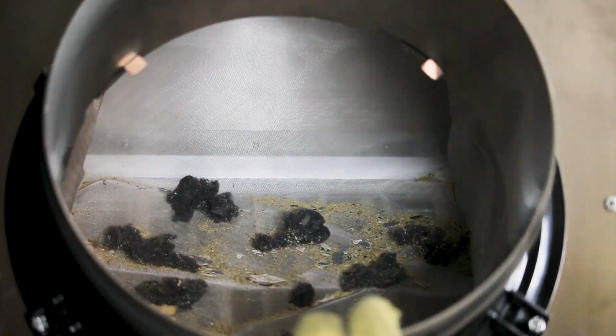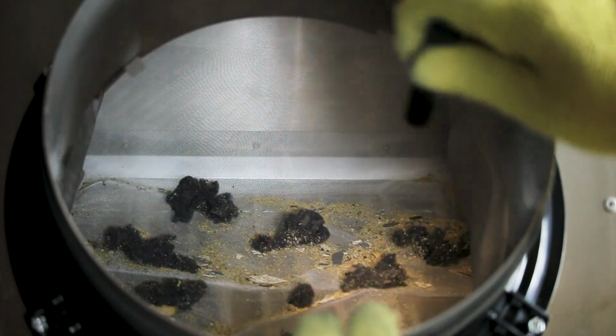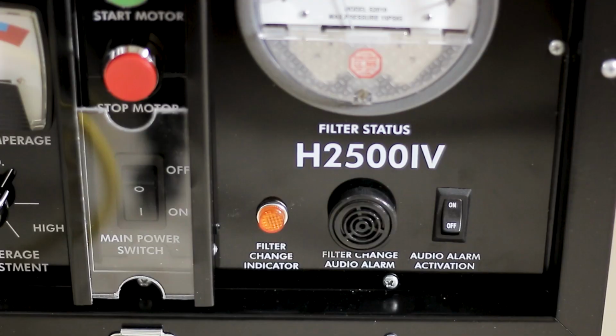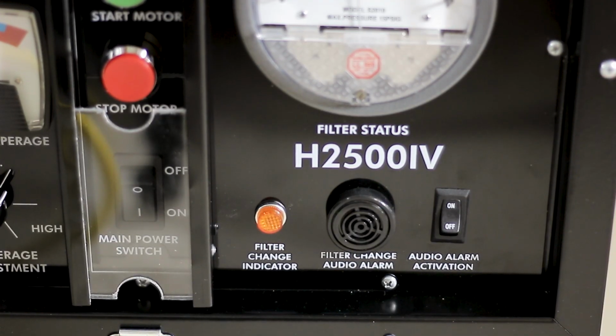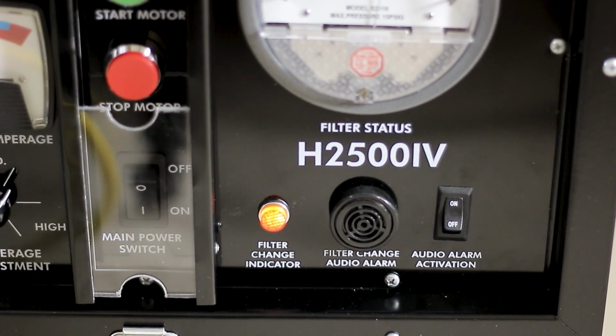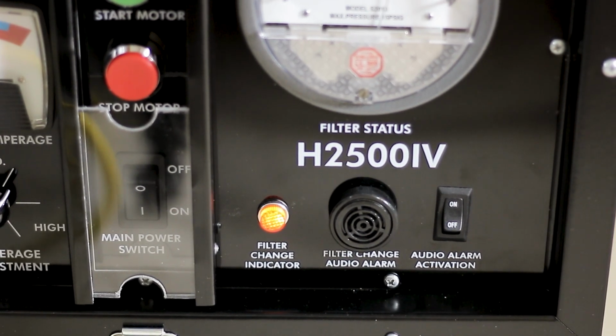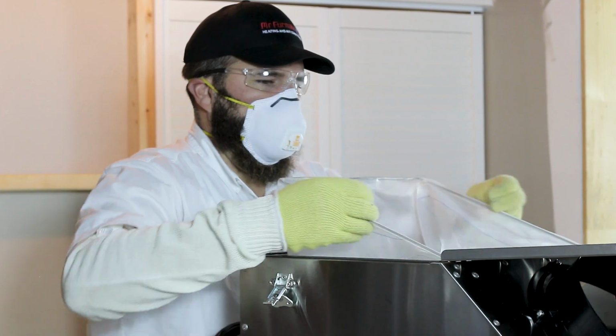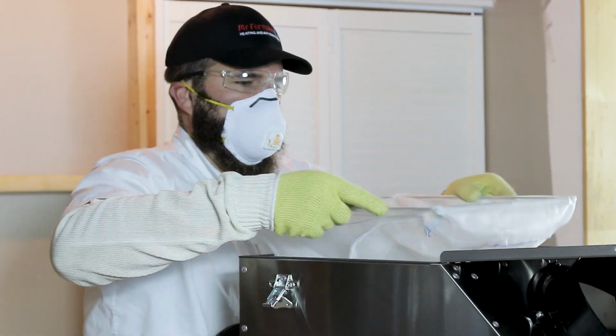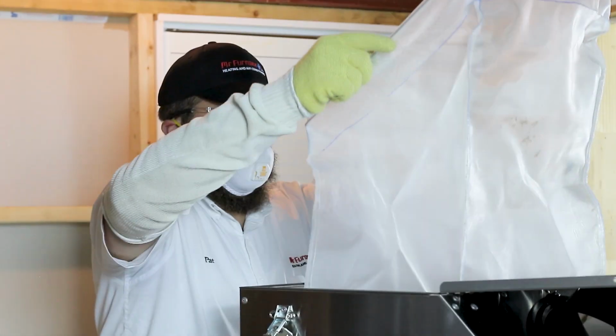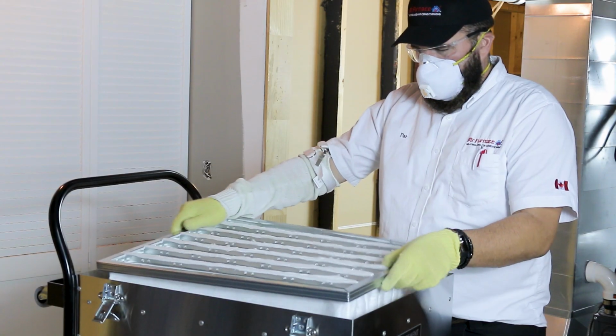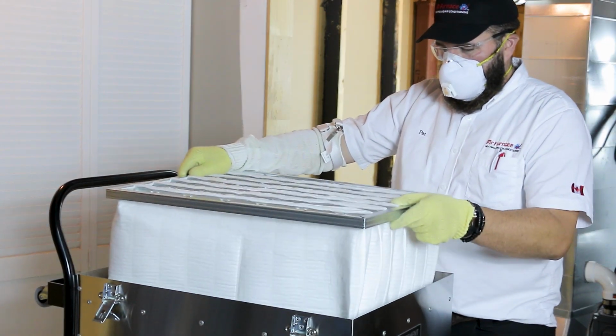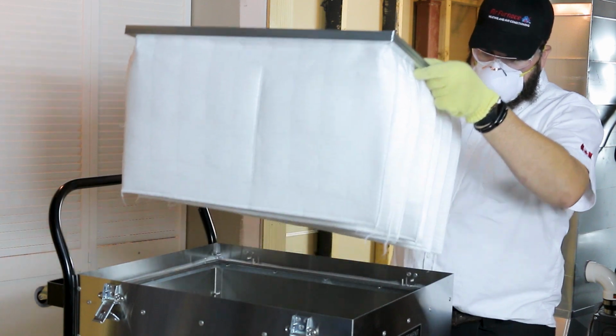In order to maintain a high airflow through the ductwork, it is essential to change the vacuum filters when they become dirty. An audio and visual alarm will activate when the airflow has been significantly reduced due to dirty filters. When this occurs, the pre-filter bag should be emptied as shown here. If the airflow is still restricted, the secondary pleated bag filter should be changed.